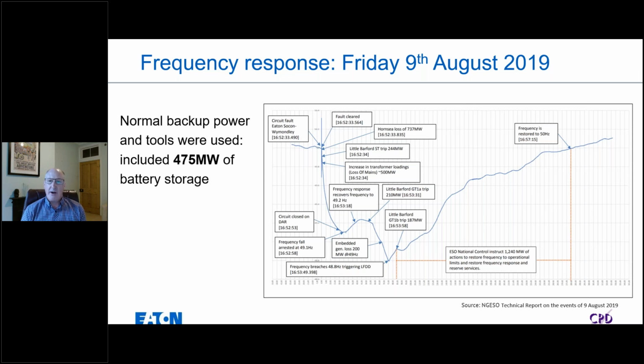So there was, as you can imagine, a very big post-mortem of this event. And this slide is actually taken from the post-event report. And if any of you were involved in the accelerated loss of mains change protection event, that was driven by this occurrence. The Energy Networks Association determined that where there were consequential renewables and embedded generation trips, very often it was driven because of using vector shift frequency sensing. And so the accelerated loss of mains change protection demanded that all generator protection relays were changed to what they call RoCoF, which is rate of change of frequency sensing, to try and prevent these events happening in future.